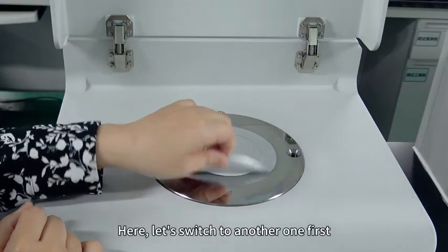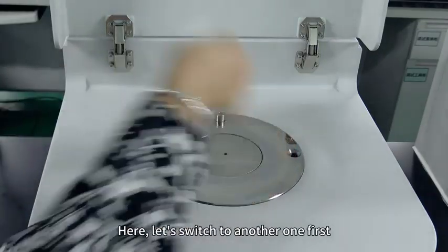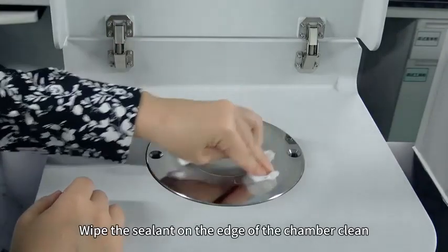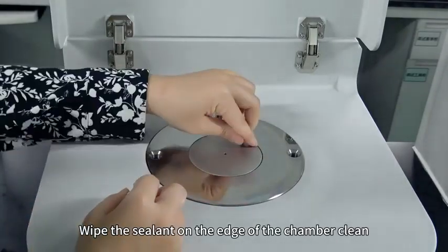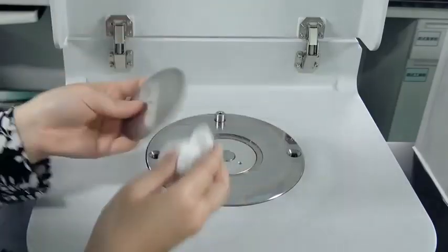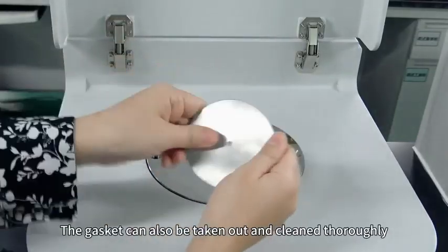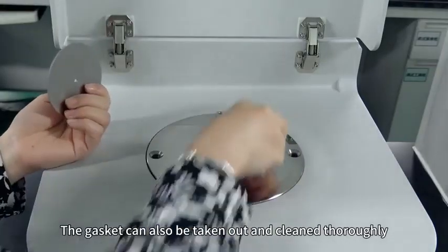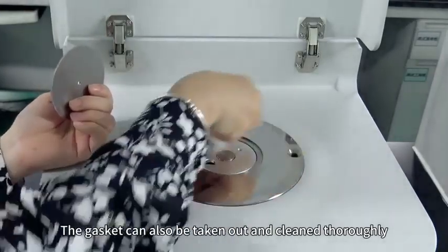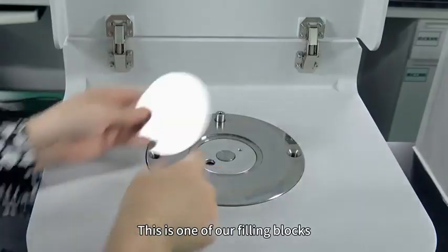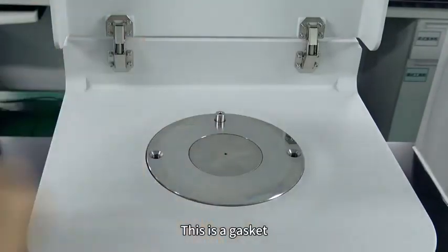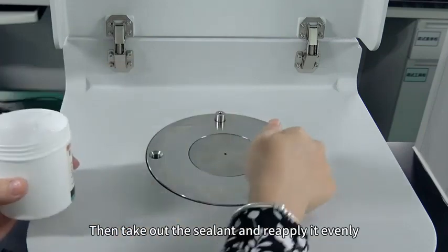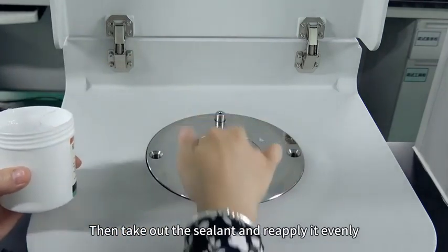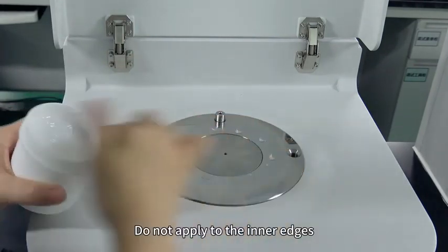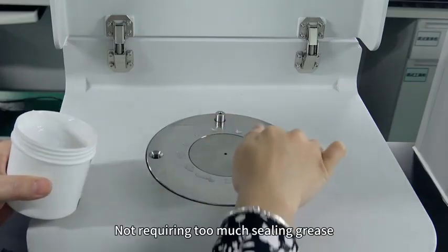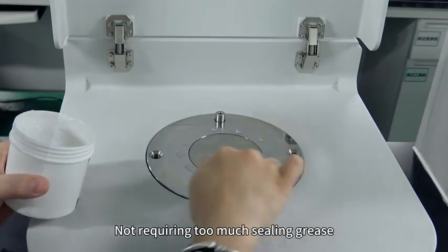Here, let's switch to another one first. Wipe the sealant on the edge of the chamber clean. The gasket can also be taken out and cleaned thoroughly. This is one of our filling blocks. This is a gasket. Then take out the sealant and reapply it evenly. Do not apply it to the inner edges, and not too much sealing grease is required.